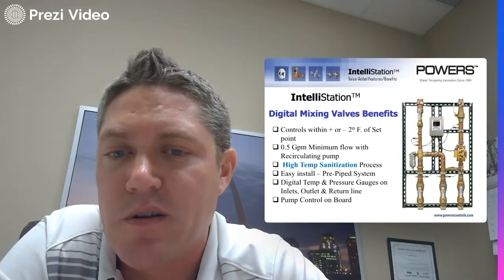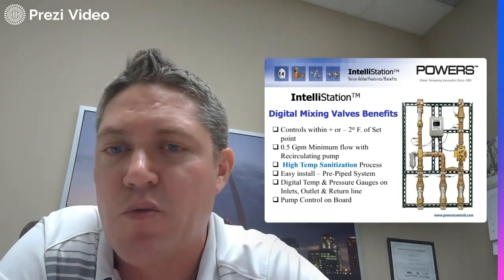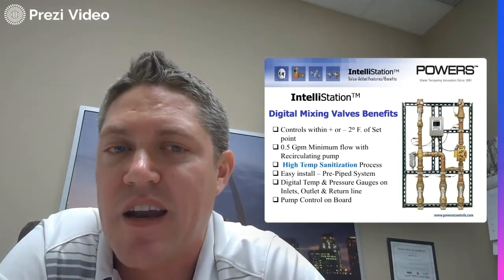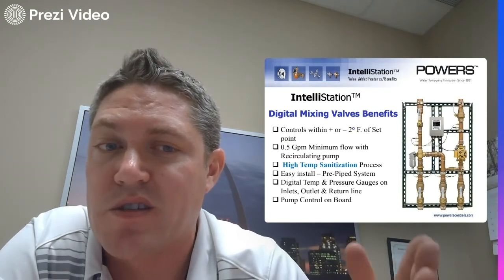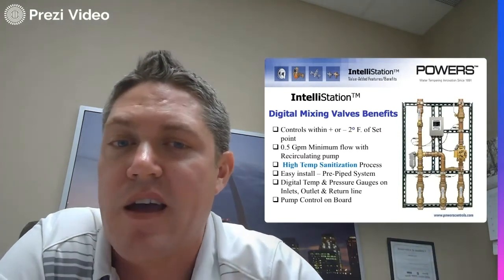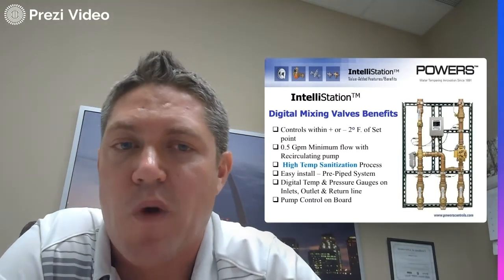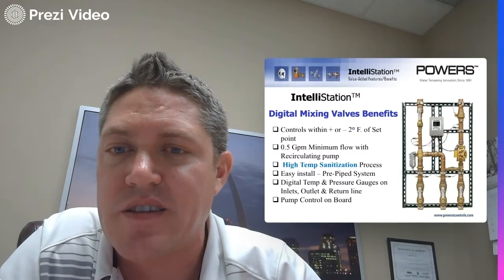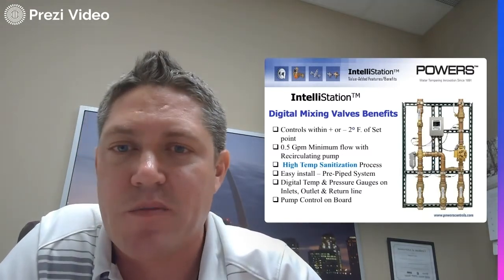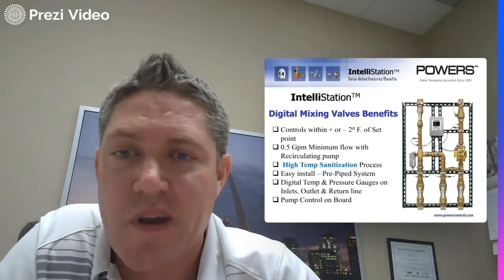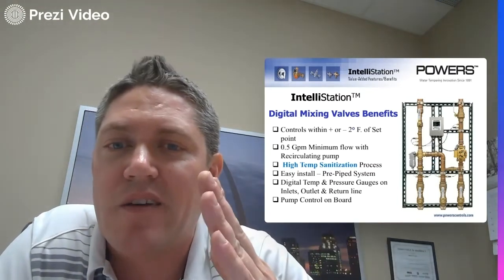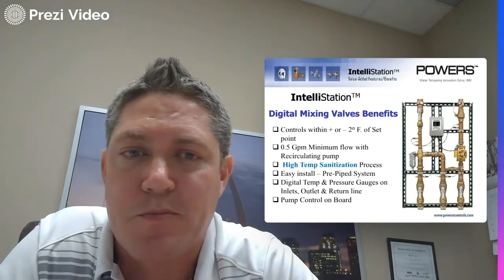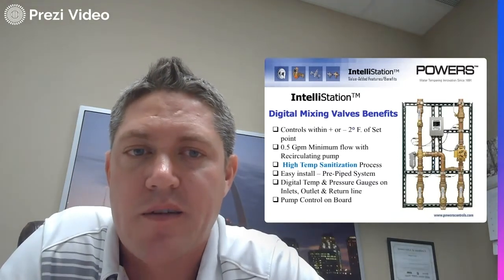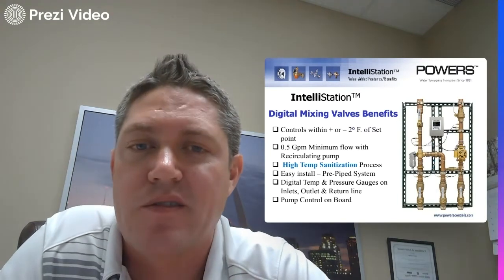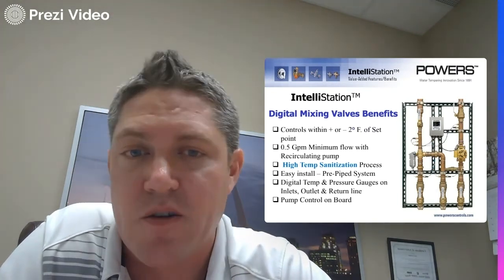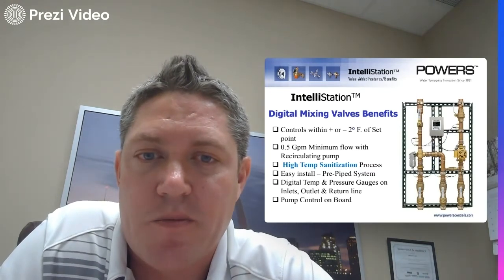Plug in your password, go into the sanitization mode, and tell it what temperature you want to run your sanitization at throughout the building, as long as your water heater source can provide that temperature. Then you set a timer. It'll raise the temperature up to say 160 degrees, as long as you're providing 160, 165 degrees from the heater, and then start, let's say, a 30-minute countdown. When that countdown ends, it'll go right back to the parameters you had set beforehand, bring the temperature back down, and go right back into controlling the temperature in that loop. So very easy to do a sanitization mode.